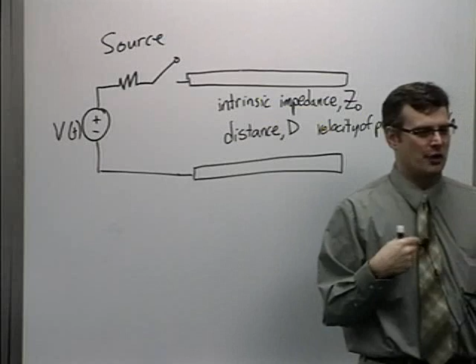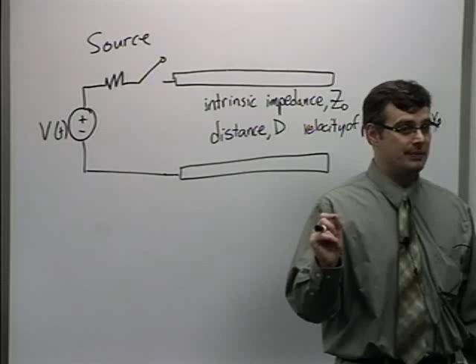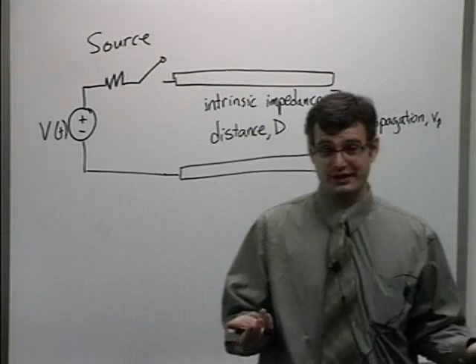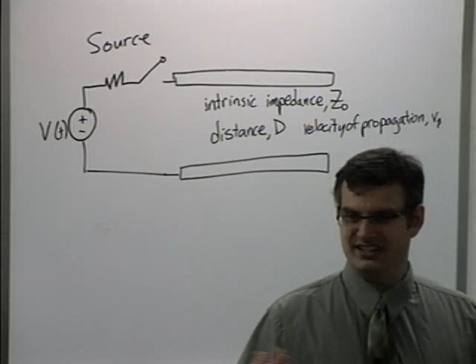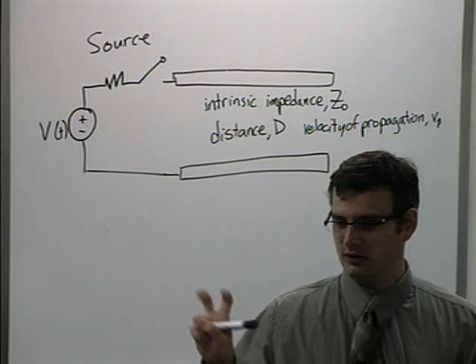And in order to do that, you need this velocity of propagation, which you'd find in the case of going from Alpharetta to downtown Atlanta, you're talking like at 60 hertz, that's such a low frequency, and the wavelength is so large, you probably don't have to worry about it. They do tend to be very picky in the power industry. Even when the transmission line approaches, say, 1/100th of a wavelength, they tend to pay attention to transmission line theory and look at things like load transformation effects and that sort of thing. And that's because they're dealing with megawatts of power transmit. You know, they don't have as much tolerance as the average motherboard designer, for example, in percent error of their signals. So these rules of thumb are always kind of contextual, right? Depending on your application, you can get a much more tighter rule of thumb than just 1/10 of a wavelength.